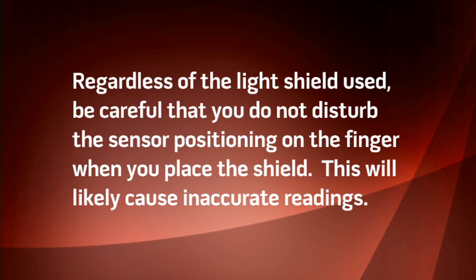If you don't have a light shield available, anything that completely shields the sensor from light will do. This could be a towel, jacket, blanket, pillow, etc. This does not include covering the sensor with your hand. Light can seep in around your fingers and interfere with the calculations. Regardless of the light shield used, be careful that you do not disturb the sensor positioning on the finger when you place the shield. This will likely cause inaccurate readings.